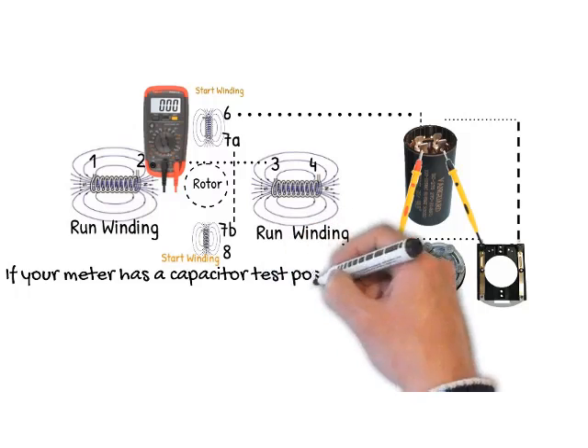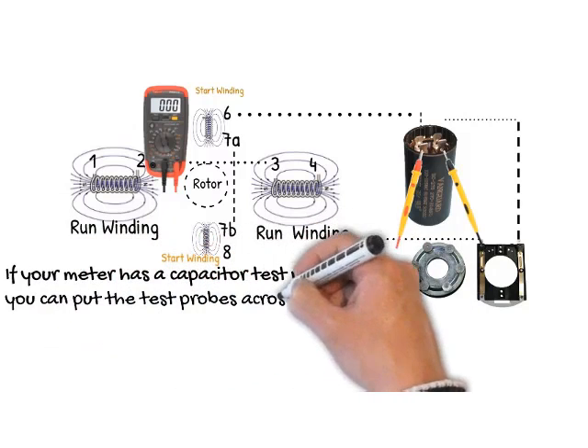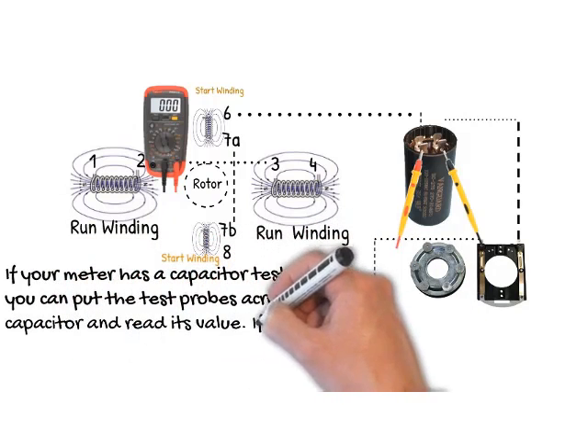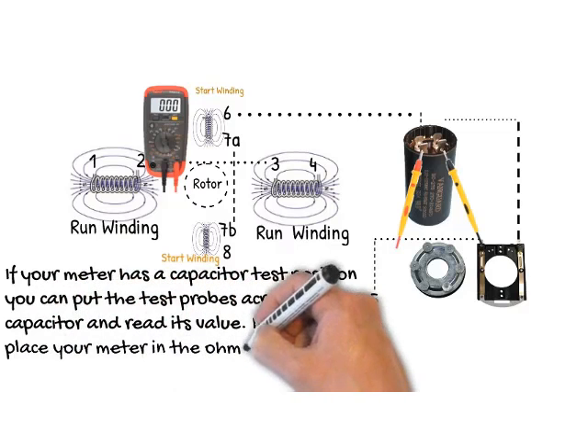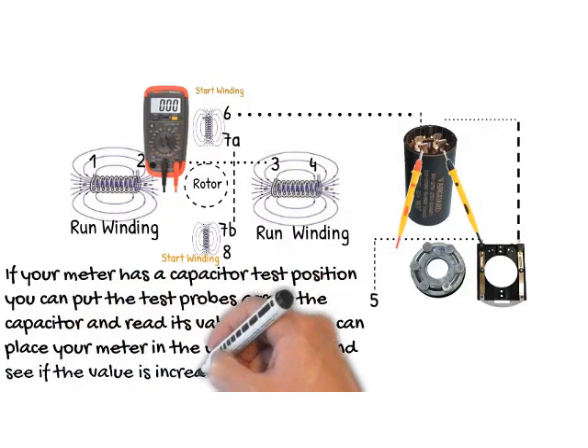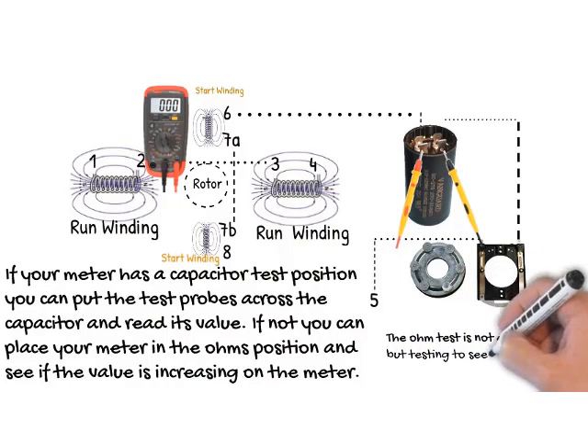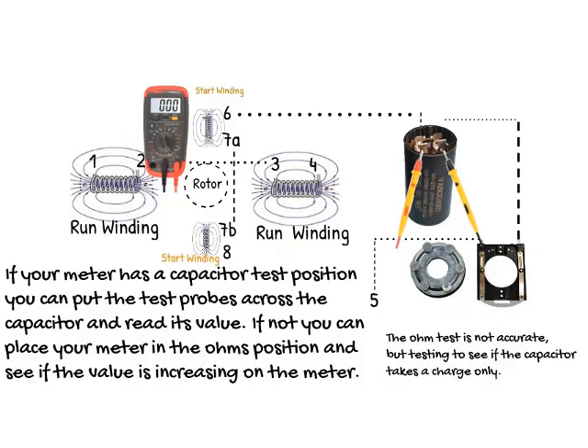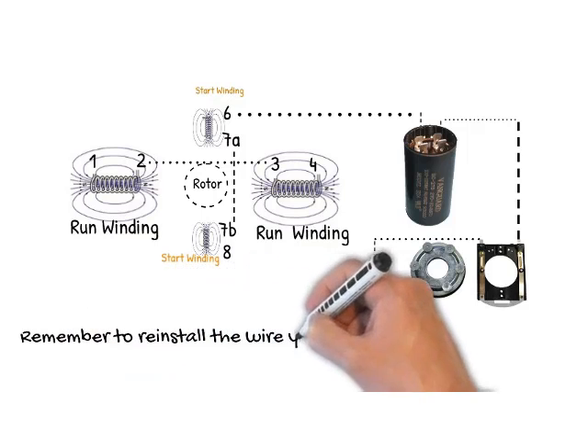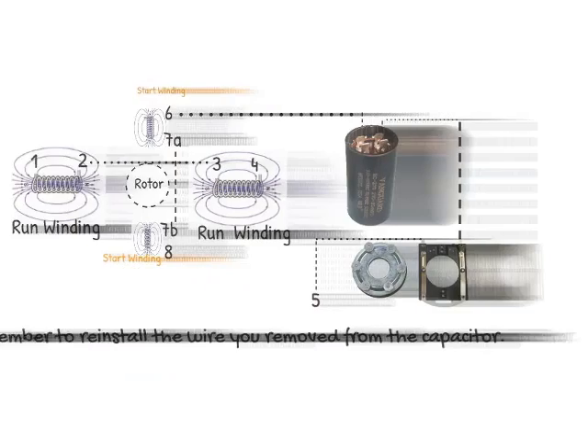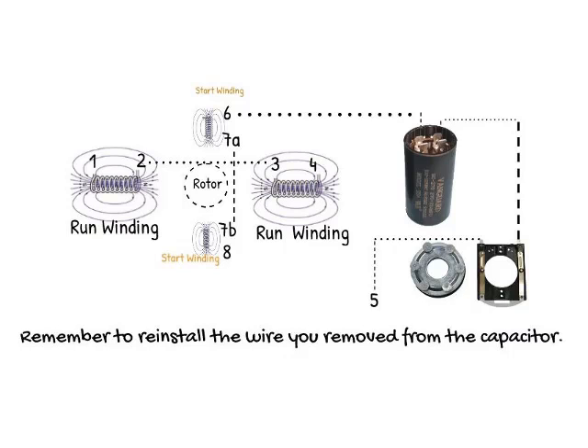If your meter has a capacitor test position, you can put the test probes across the capacitor and read its value. If not, you can place the meter in ohm's position to see if the value is increasing on the meter. The ohm test is not accurate, but testing to see if the capacitor takes a charge. Remember to reinstall the wire you removed from the capacitor, as indicated by the arrow.